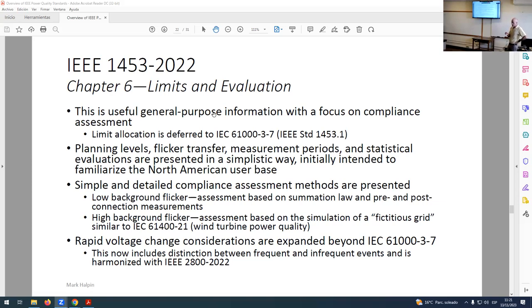It looks kind of simple, but getting it right is not simple at all. Okay, so I don't agree with it, but that's not the point. I'm just one person. Okay, this is what's in 1453. But of course, if a utility company is going to adopt the flicker meter and limits based on IEC, then you've got to have some way to assess compliance. These are realities, right? And before 1453, in the U.S., in the IEEE arena, we didn't have these kinds of recommendations for utility engineering, right? So 1453 made a pretty good contribution.